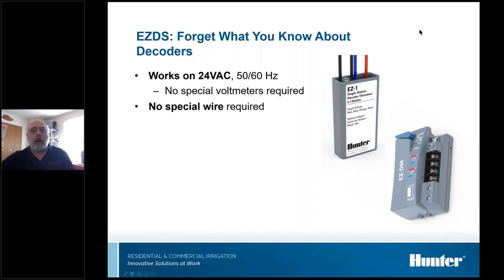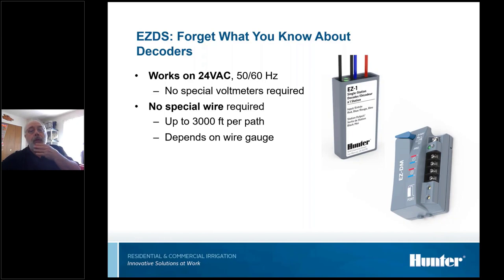You can use any kind of connector you want on it. Use King wire nuts if you want, it doesn't matter. The wiring distances are dramatically decreased though. With 12 gauge wire, we can go to 3,000 feet. With 14 gauge wire, it's about 2,200, and it goes down from there. It's very dependent on wire gauge. We can get away with using smaller wire, but our distances become drastically reduced.